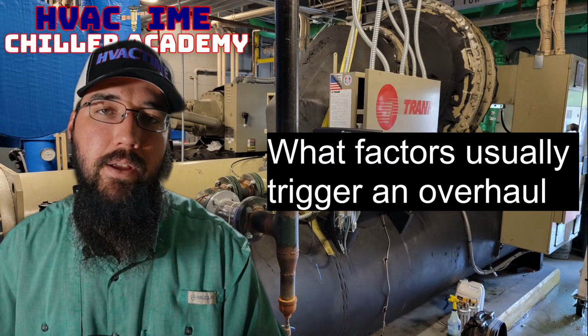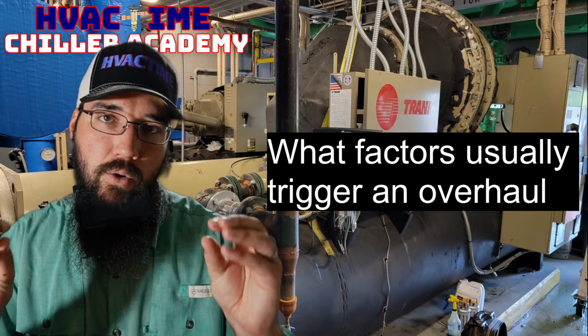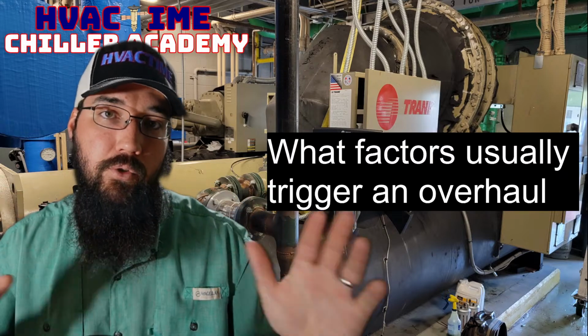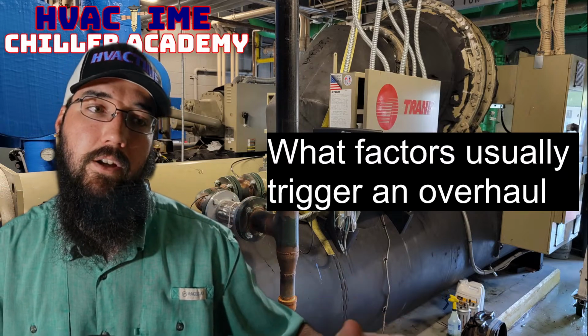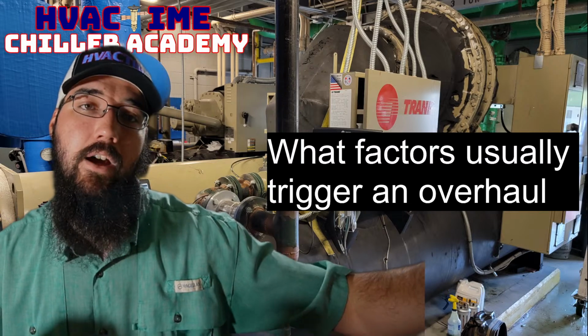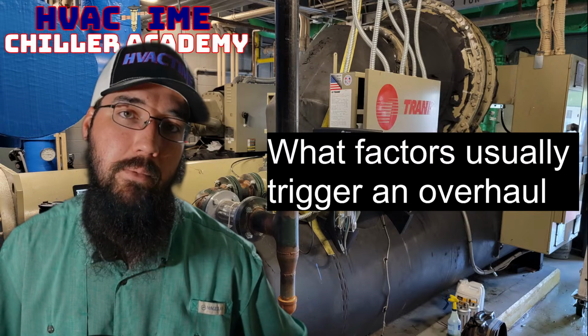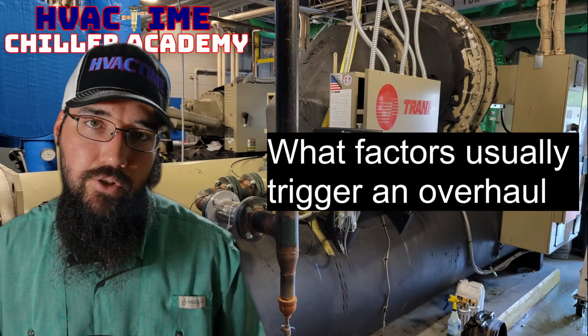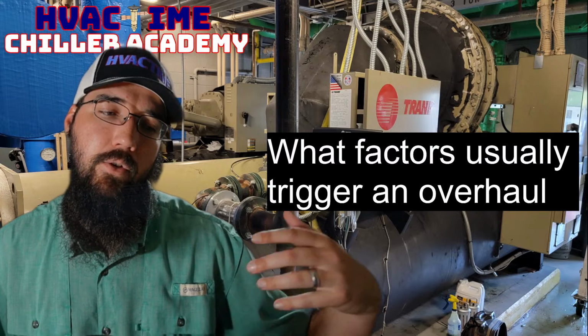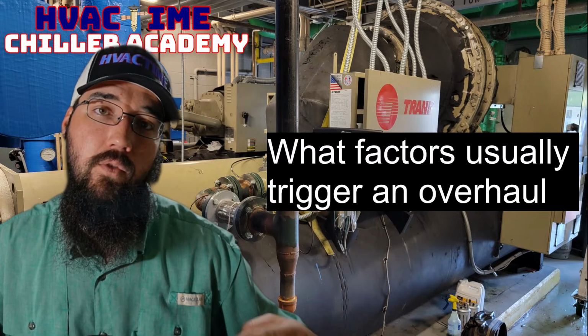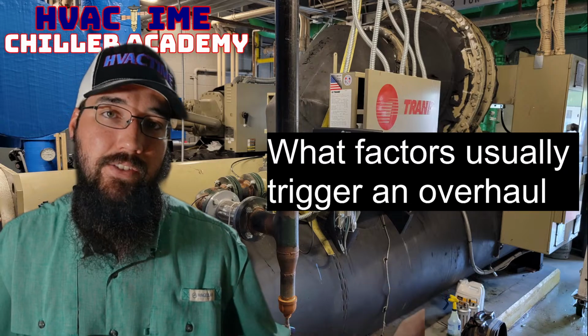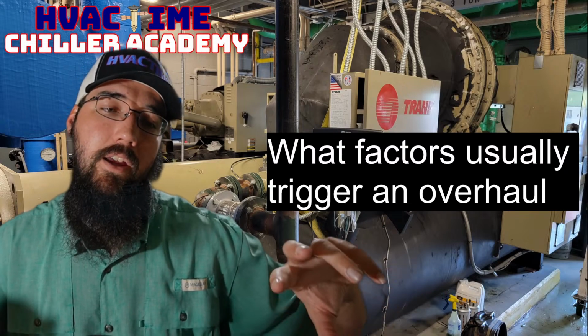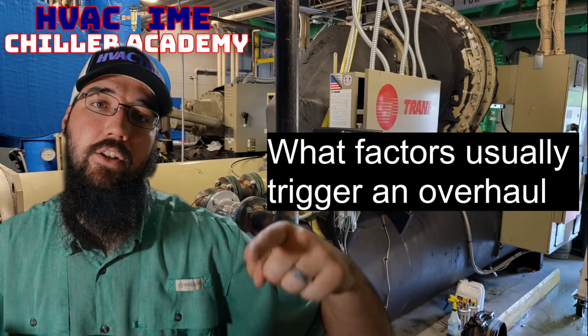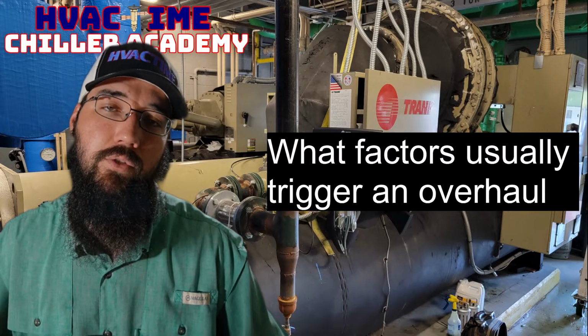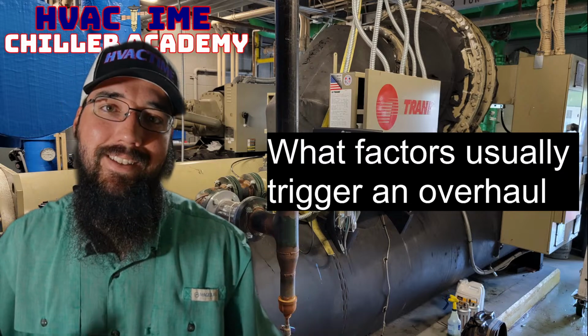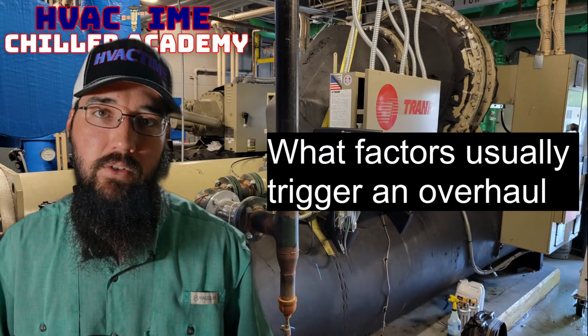It depends on the manufacturing process itself and how much tolerance there is before you start messing up their product, because if you get too far outside those ranges, now their product is being affected, which hurts their bottom line. So having chillers down is not an option. In that environment, they go through a routine overhaul cycle whether the chiller has symptoms or not. They go in on a schedule and do a continuous overhaul cycle of those centrifugals to prevent downtime as much as possible.